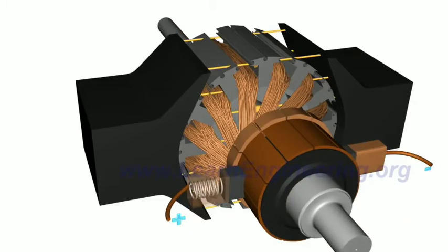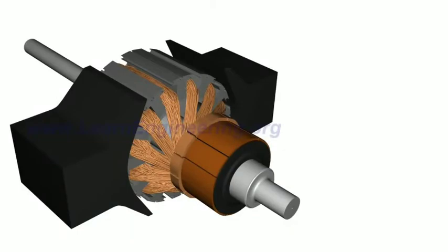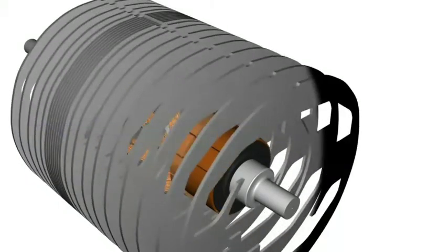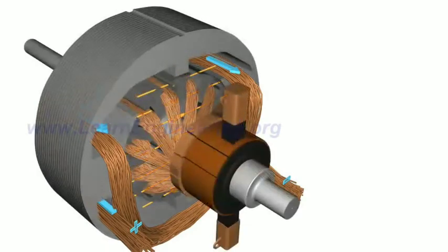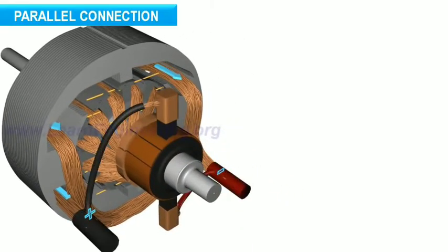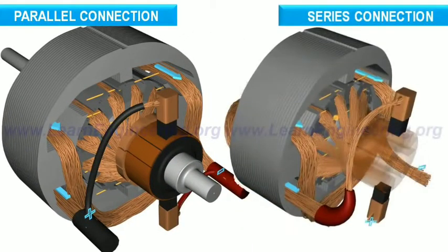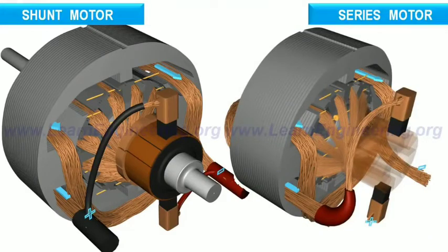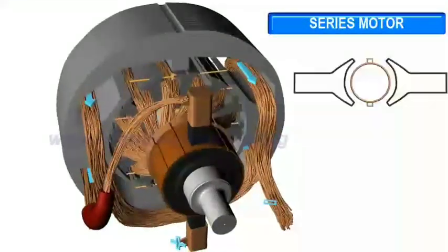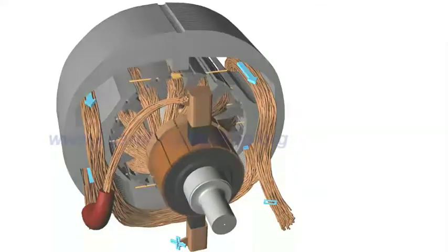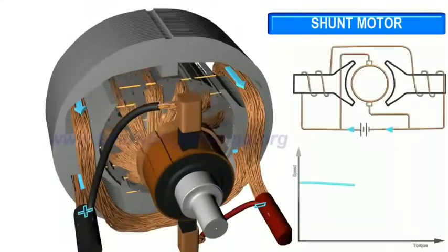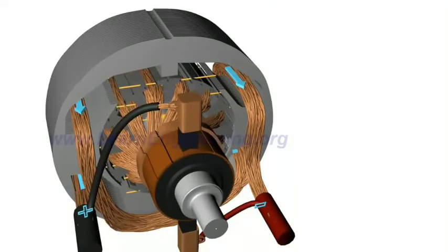Applications of DC motor. The use of DC motors in control systems ranges from very low energy, delicate control applications, to heavy-duty control operations in elevators and vehicles. In general, PM types are used for motors of less than 10 horsepower, 7.5 kilowatts, and wound field types for units up to about 100 to 200 horsepower, 75 to 150 kilowatts.